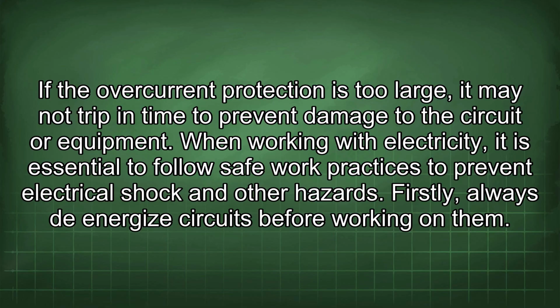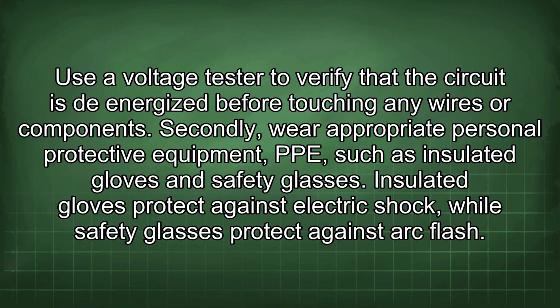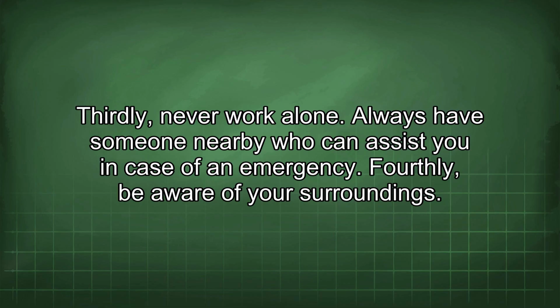Firstly, always de-energize circuits before working on them. Use a voltage tester to verify that the circuit is de-energized before touching any wires or components. Secondly, wear appropriate personal protective equipment, PPE, such as insulated gloves and safety glasses. Insulated gloves protect against electric shock, while safety glasses protect against arc flash. Thirdly, never work alone. Always have someone nearby who can assist you in case of an emergency.